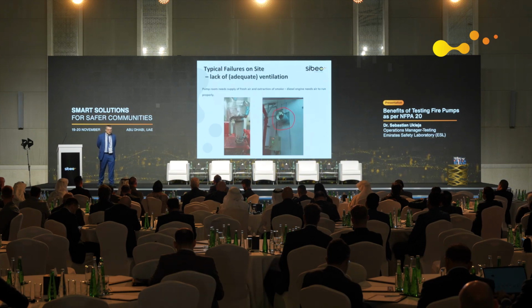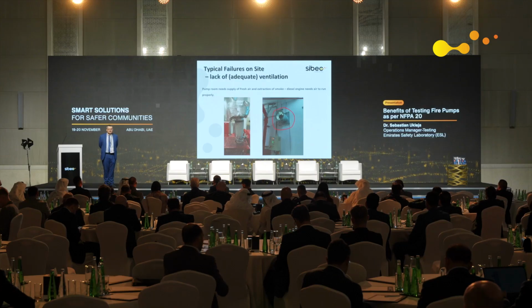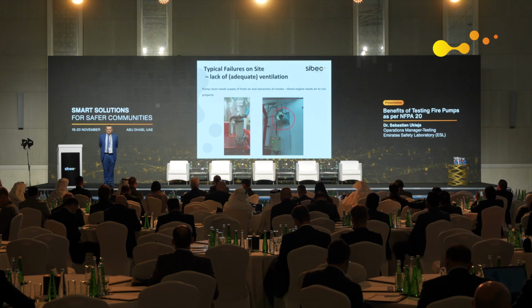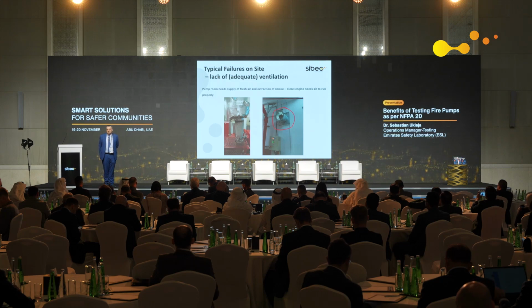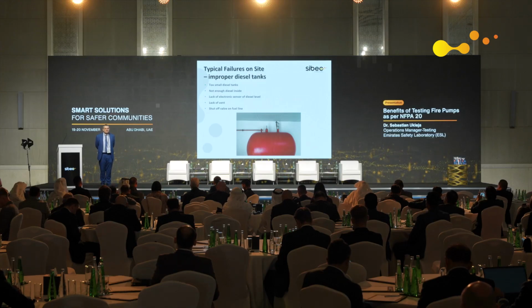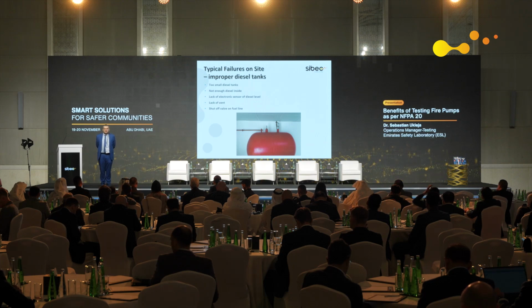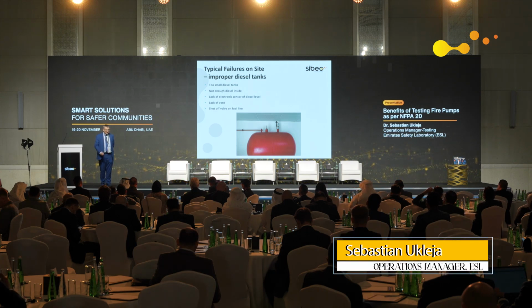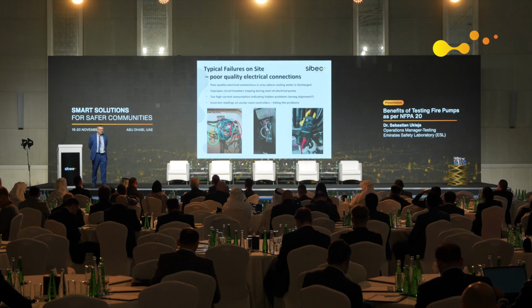A few more issues to add, such as ventilation. As you know, a diesel engine requires air to operate, like your car requires air to breathe, unless you have an electric car. If there is not enough air provided to the pump room, the diesel pump would basically choke and stop operating. And from the diesel pumps, we have also observed a whole bunch of problems with the diesel tanks. They are either too small, or they don't have ventilation, or they are not filled properly in terms of the amount. And I'm talking only about new projects. So those are, let's say, auxiliary situations, but they also affect the pump performance.